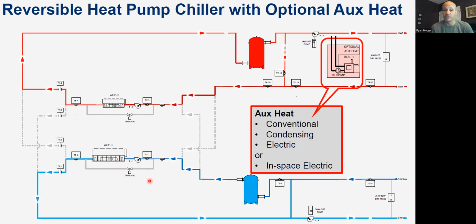And if I need a ton of heating, and I don't need any cooling because it's a smaller building, I can make both of these run in heat. So wintertime, I can have 2 machines running heat. Summertime, I can have 2 machines running cooling. And in the spring and fall, I can have one doing heat, one doing cooling. Because maybe the east side needs heating in the afternoon, but the west side is going to be beat on by the sun and they need cooling, right?